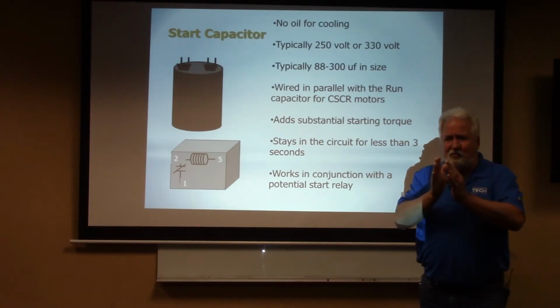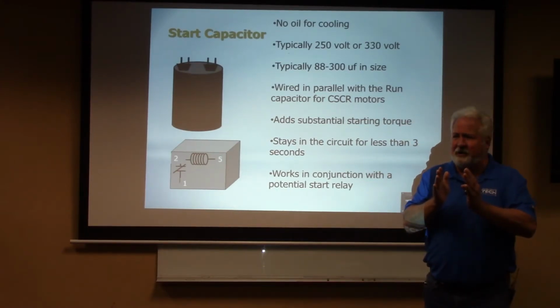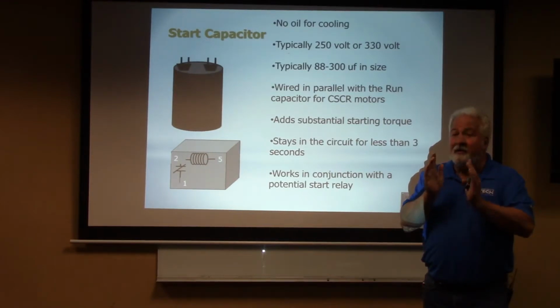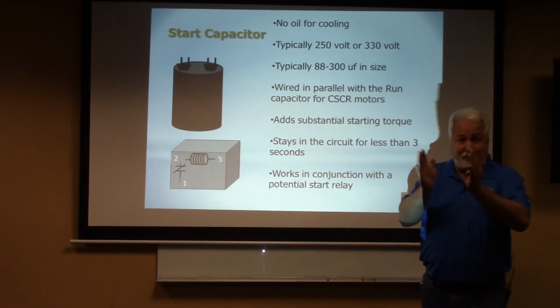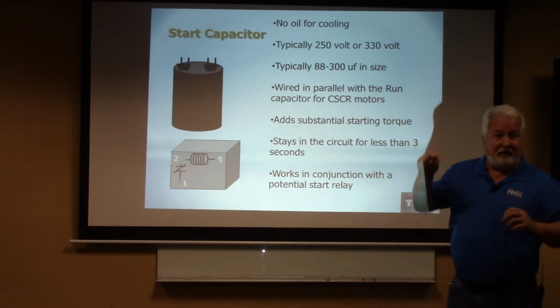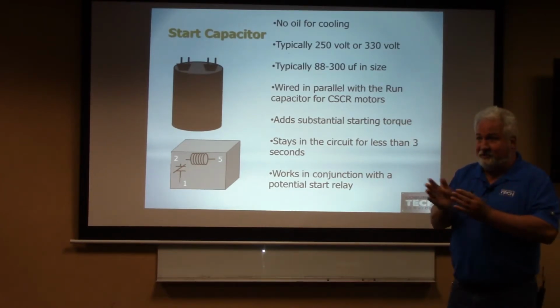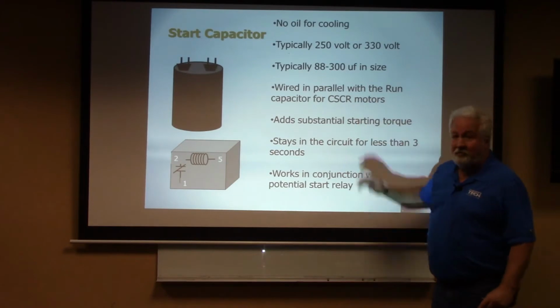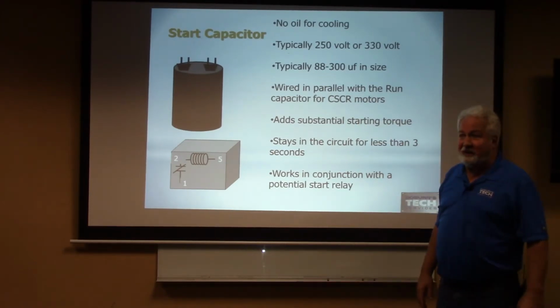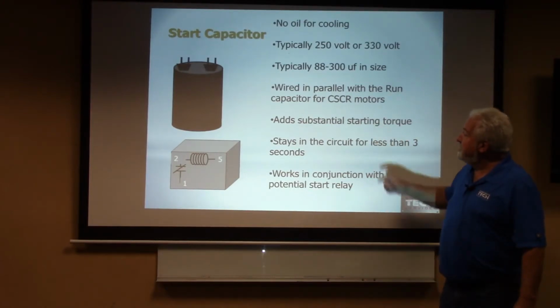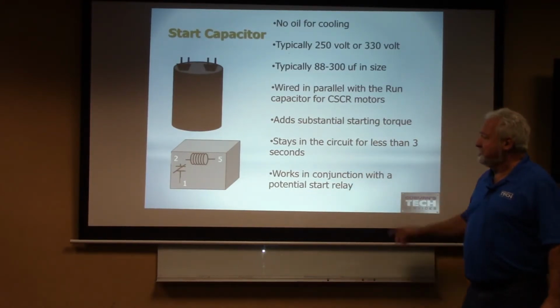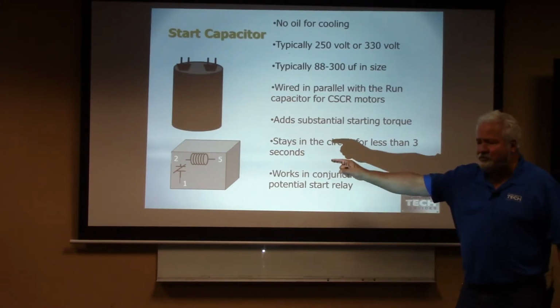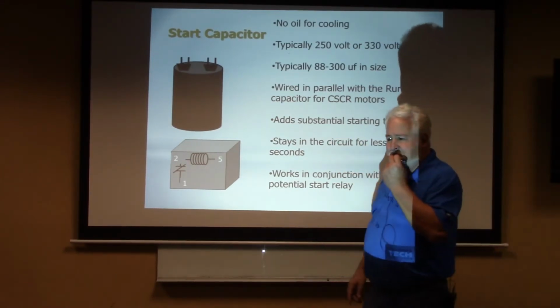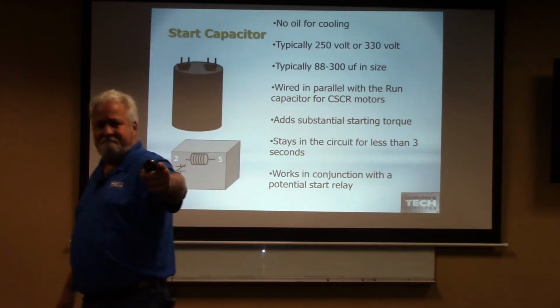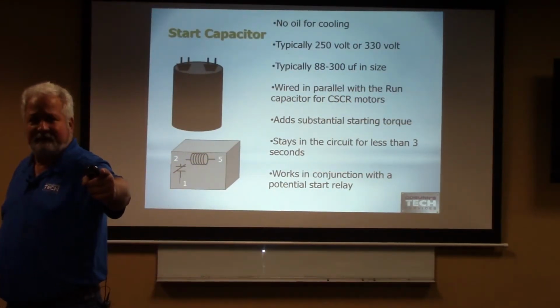When I take two capacitors and wire them in parallel, what happens to that? They add together, right? When they're in parallel, right? Parallel, they add. Series, they lose, right? Okay, so start capacitor and the run capacitor, what's going to happen now to that starting torque? Yeah, it's going to go way up. Adds substantial starting torque. Stays in the circuit for less than 3 seconds. It works in conjunction with a potential start relay. So let's think about that. You got him, and he's your run capacitor, is that right?